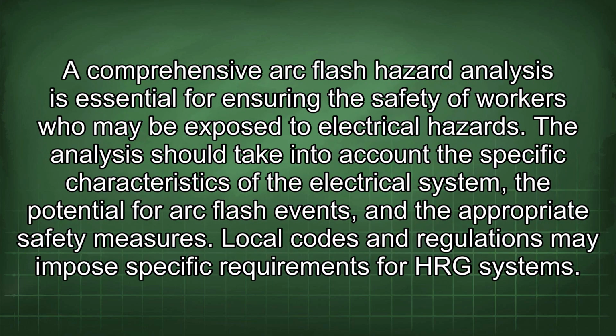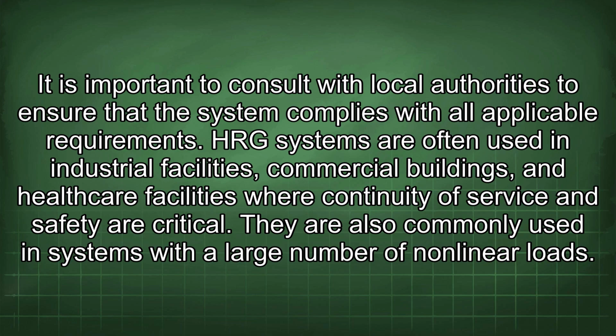A comprehensive arc flash hazard analysis is essential for ensuring the safety of workers who may be exposed to electrical hazards. The analysis should take into account the specific characteristics of the electrical system, the potential for arc flash events, and the appropriate safety measures. Local codes and regulations may impose specific requirements for HRG systems. It is important to consult with local authorities to ensure that the system complies with all applicable requirements. HRG systems are often used in industrial facilities, commercial buildings, and healthcare facilities where continuity of service and safety are critical. They are also commonly used in systems with a large number of nonlinear loads.